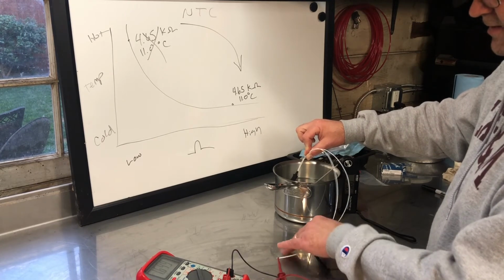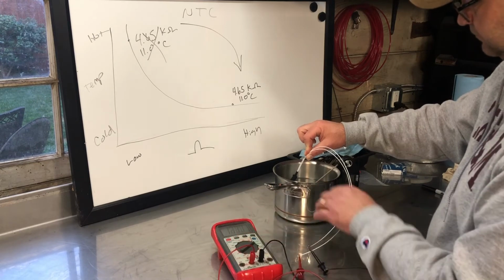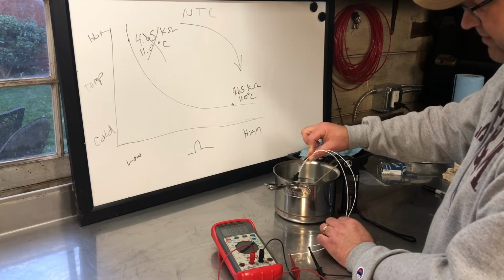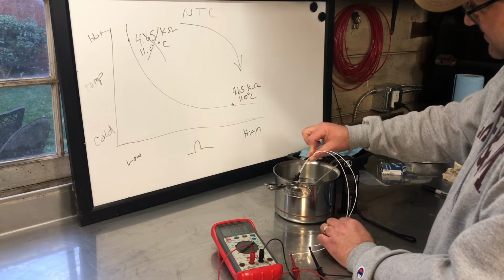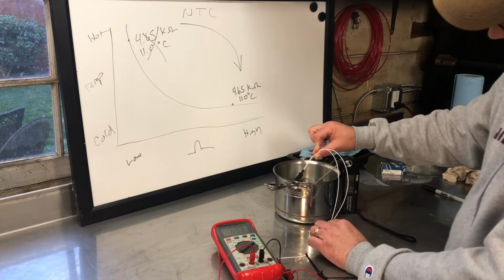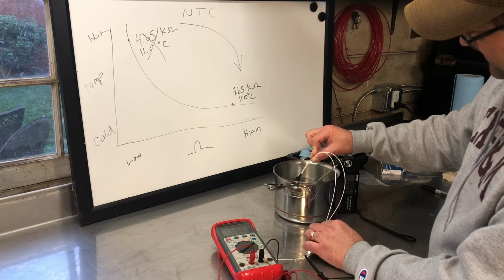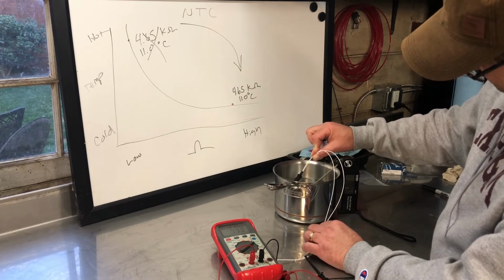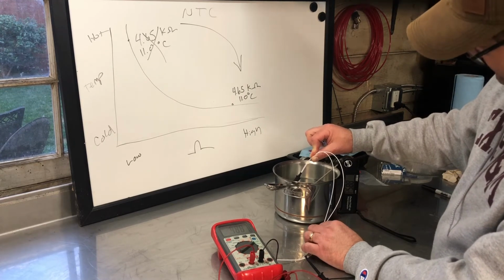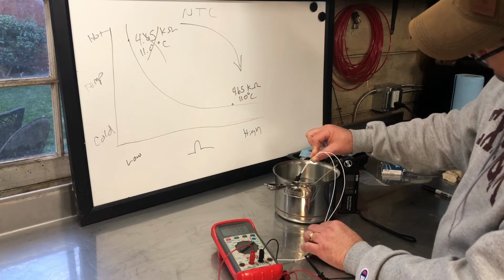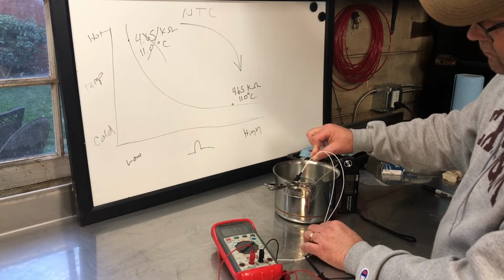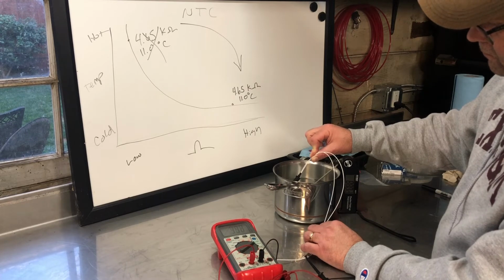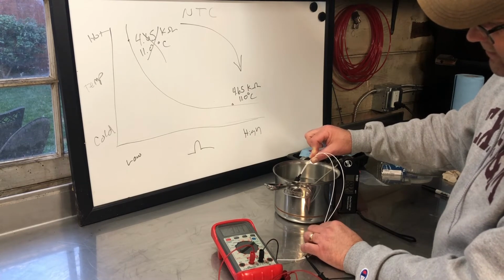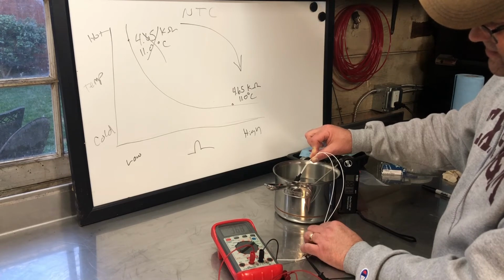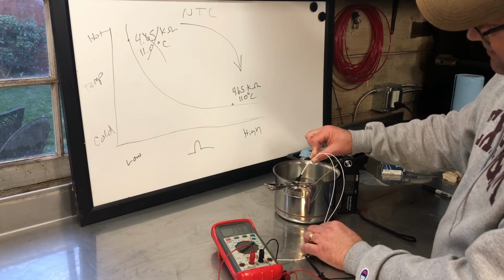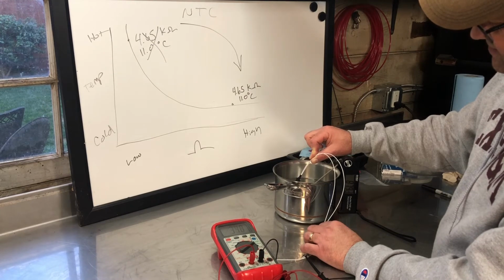We're at 2 kiloohms and dropping fast. This will probably be down into the hundreds of ohms. We'll wait for the resistance value to settle out and see what the temperature is. This might be a little harder to get a good reading on because the temperature is dropping pretty quickly. We're going to wait for that resistance value to slow down and maybe even start creeping back up. That's how we know the temperature sensor is saturated with heat.